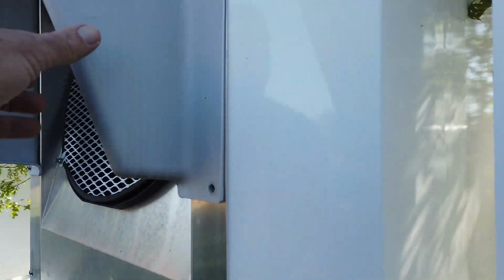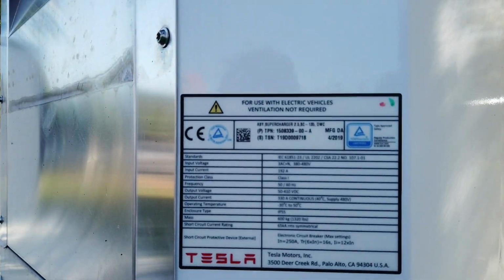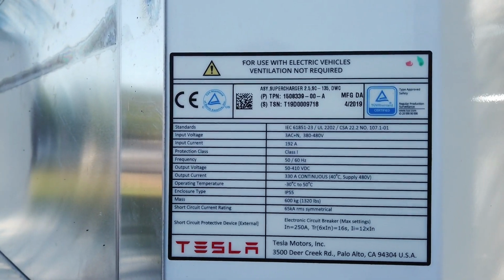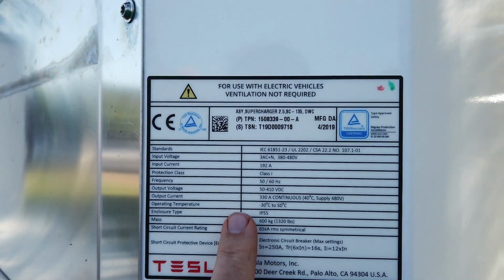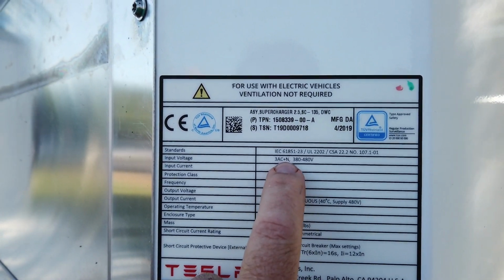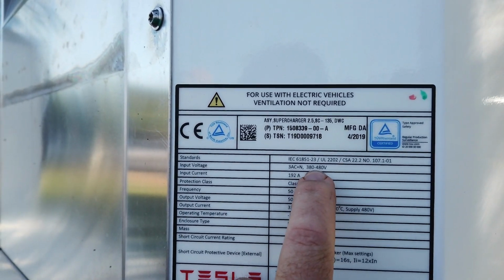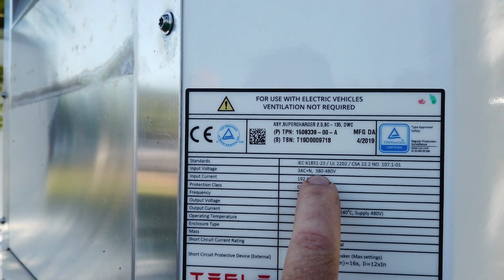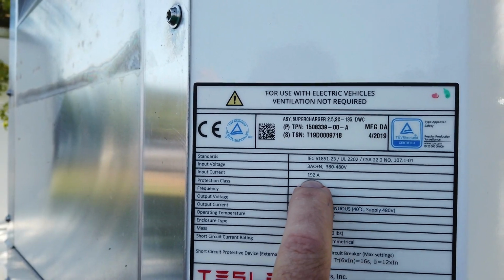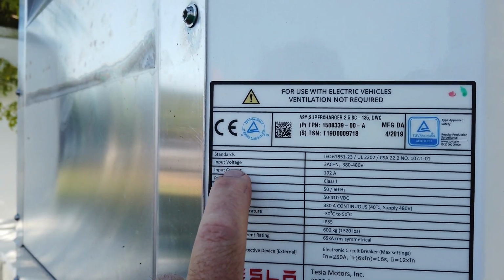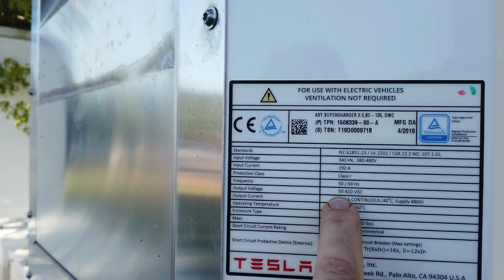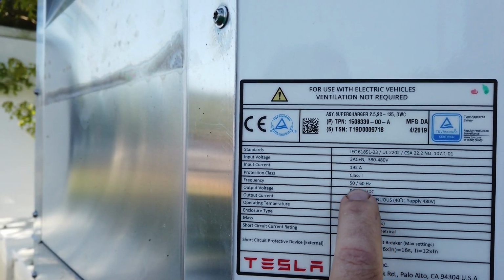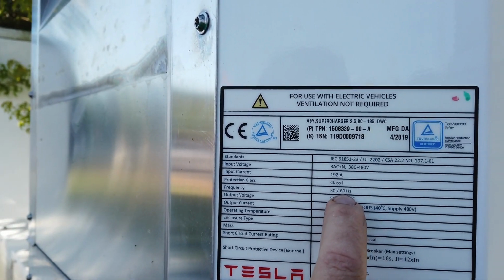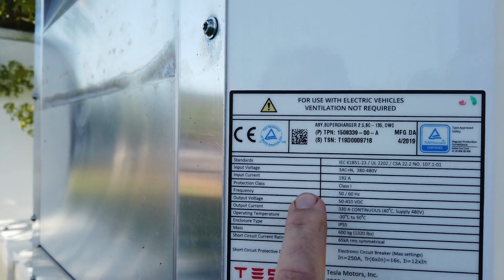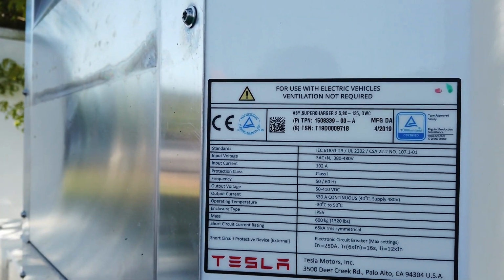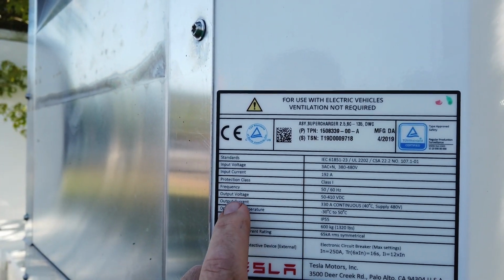But we do have this very handy dandy data plate on it, and we can read what it says. It very clearly says it's 3-phase, 380 to 480 volts, 192 amps. That's the input voltage and input current. 50 to 60 hertz — the United States uses 60 hertz, Europe uses 50 hertz. So apparently this doesn't care if it's 50 hertz or 60 hertz, you can plug it in just the same.